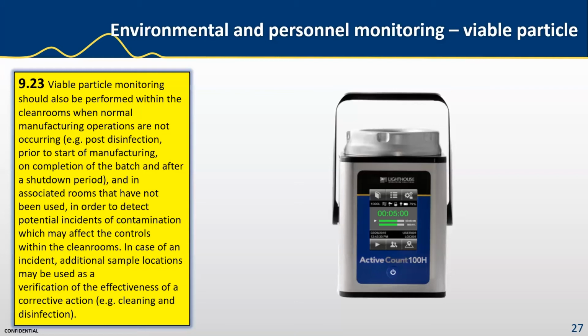Again, you can find these standards in our Knowledge Center, and there are technical papers written about these standards. But effectively, what this section is talking about is the use of additional monitoring to verify that rooms that are adjacent to your main core aseptic processing are frequently monitored so that you are not picking up any type of contamination and bringing it into the aseptic process core. So that's really important to understand, and you can achieve that with these small, easy to use portable air samplers.